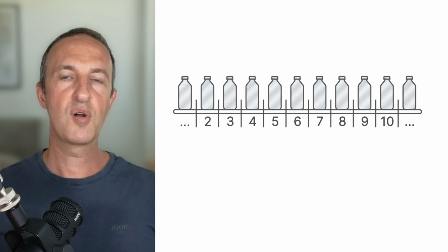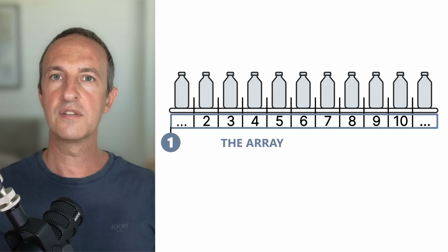A shift register is a layer of software that you add to your PLC application and that tracks items as it moves along a conveyor belt or a conveyor chain. It does this by shifting data from one position to the next, matching the physical movement of the actual products on your line. So as each product moves forward, its associated information moves with it, step by step through the line.